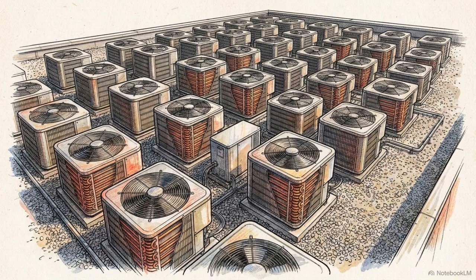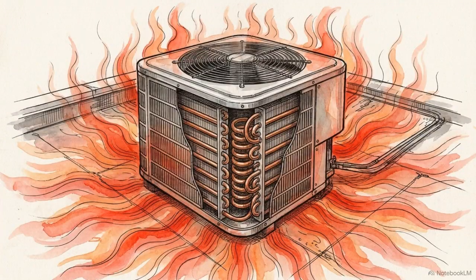When we look at commercial scaling, the air-cooled condenser is the global standard for residential split systems, window units, and VRF architectures. They require zero water connections and demand low maintenance. Their major limitation is that extreme ambient heat severely limits their efficiency, as the temperature gap between the hot refrigerant and the hot outside air narrows.